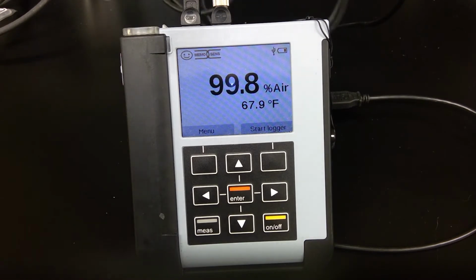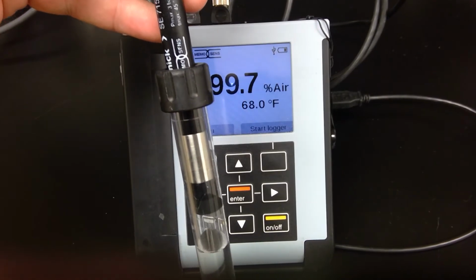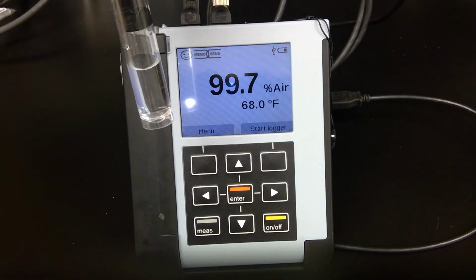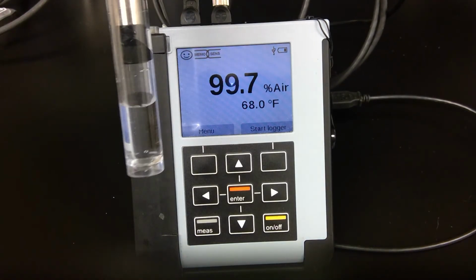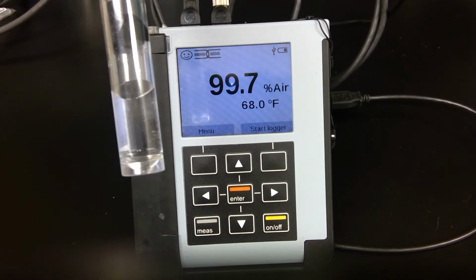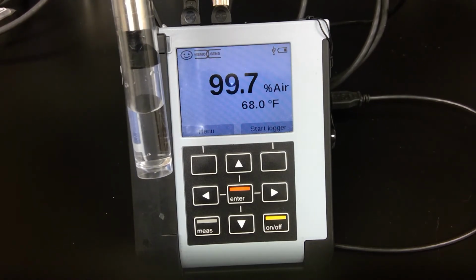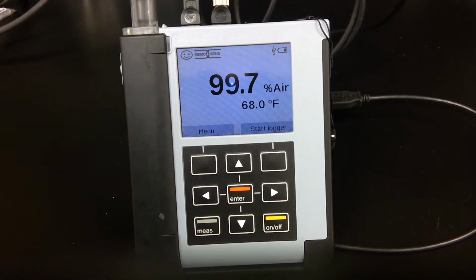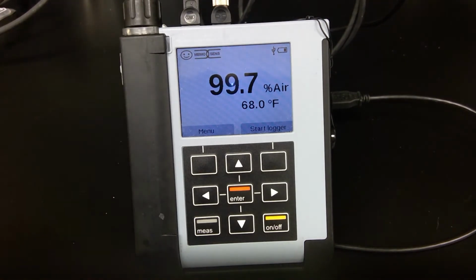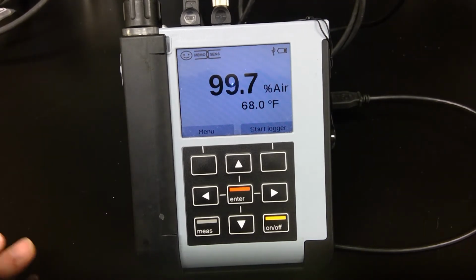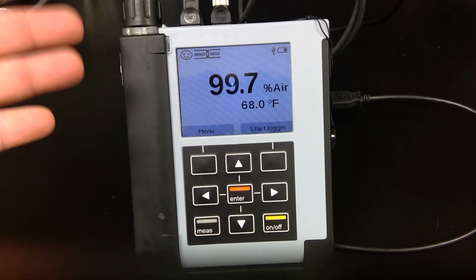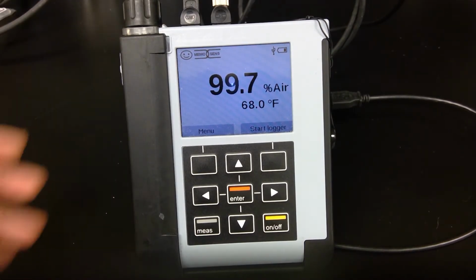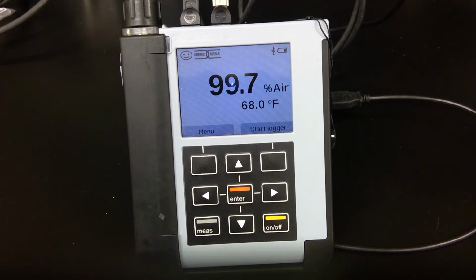So what I did, if you see here, is I took the 715 and I put a little bit of water, just tap water, in the bottom of this little calibration beaker. And keeping in mind, don't let the probe touch or immerse into the water. Just keep it slightly above the water. The reason we do that is it's much simpler when you do your setup for calibration to go ahead and put in 100% humidity than trying to figure out what the actual air humidity is where you're trying to make the measurement. You can do it, but doing it this way ensures that it's 100% humidity inside the beaker, and it makes it a much simpler calibration.